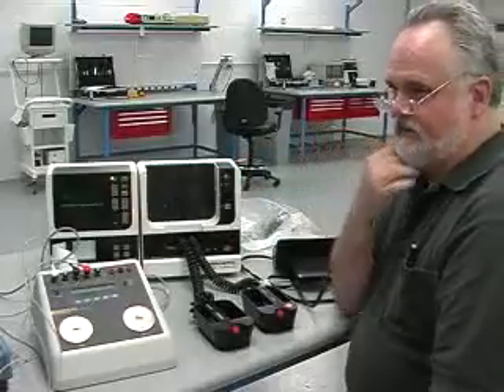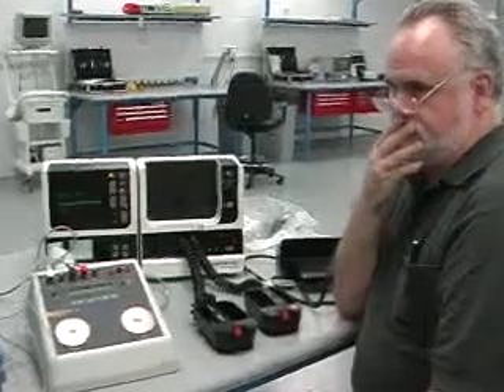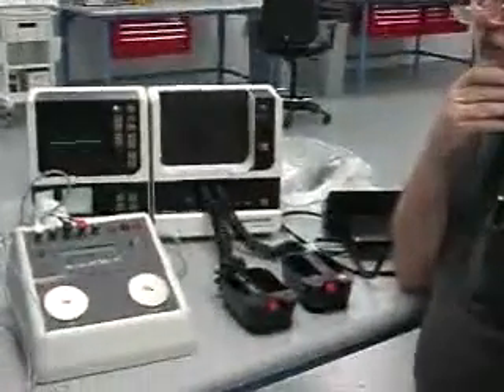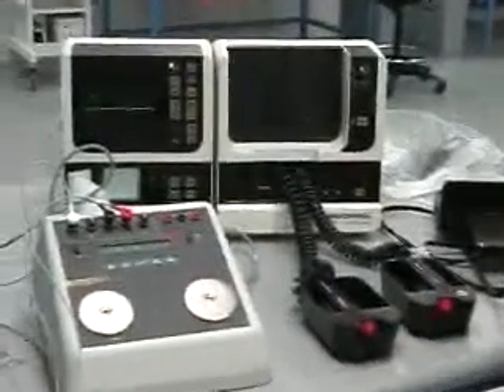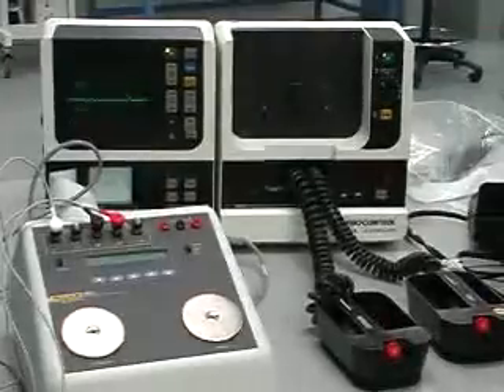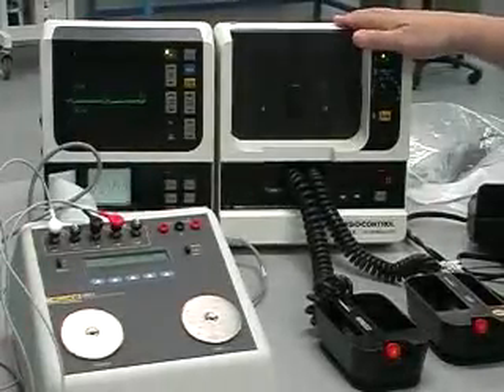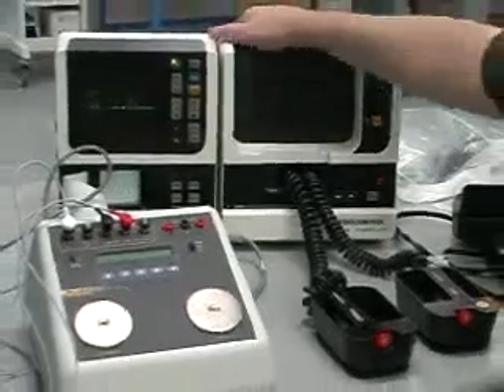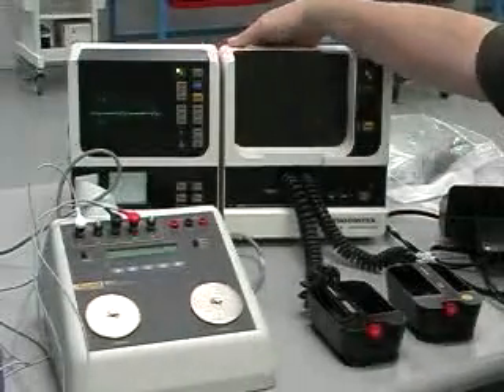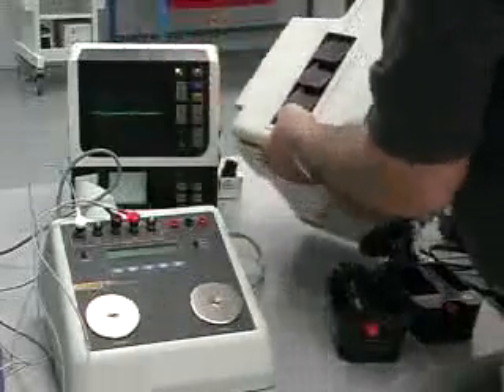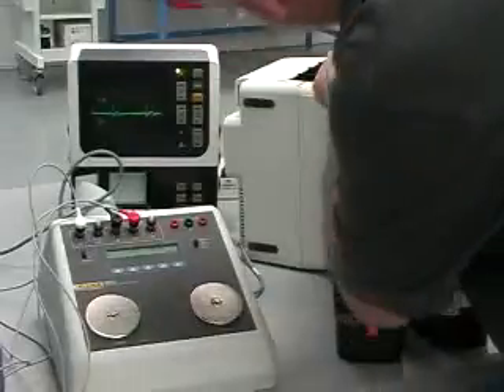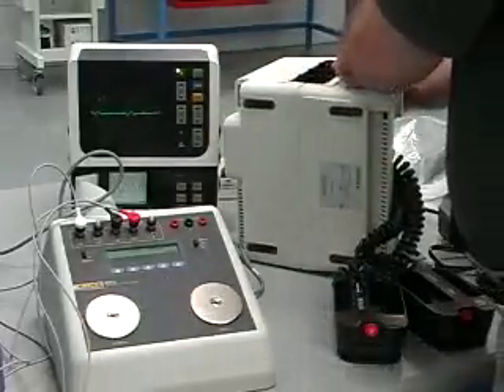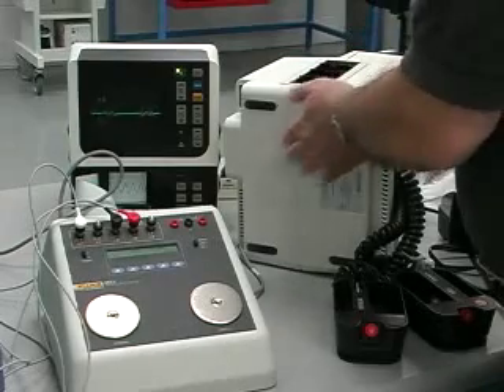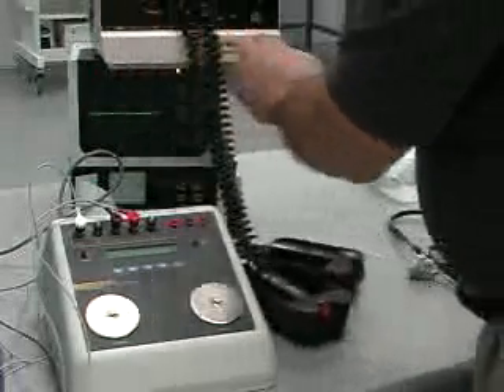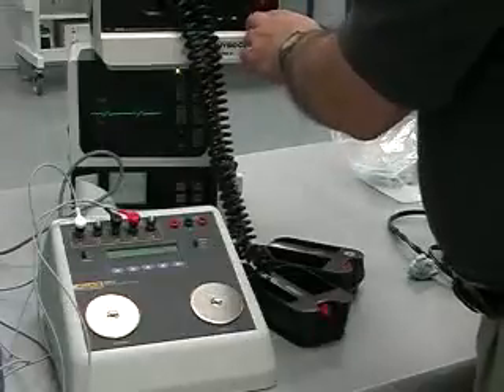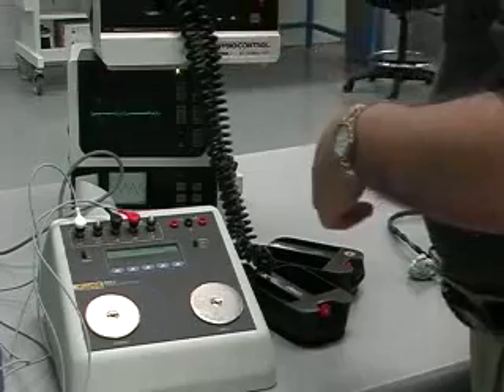Yeah. No, I thought that there is an electrical connection between the monitor and the defibrillator, and the moment of releasing the energy is established by the monitor. Yes, it is. Yeah, we could disconnect these two, and electrically there's an optical connector between these two. Right within here, there are some optical sensors, and that does communicate that information over to the defibrillator. Because right now, sync won't work. Nobody to connect to.